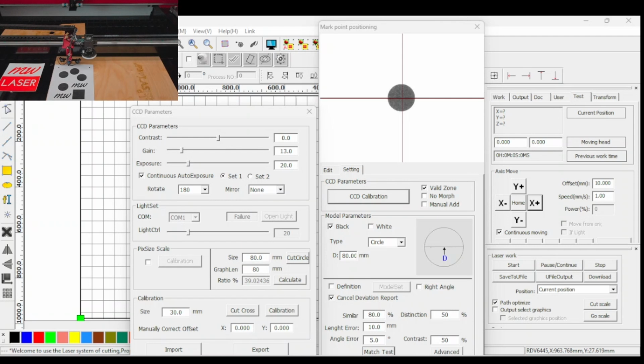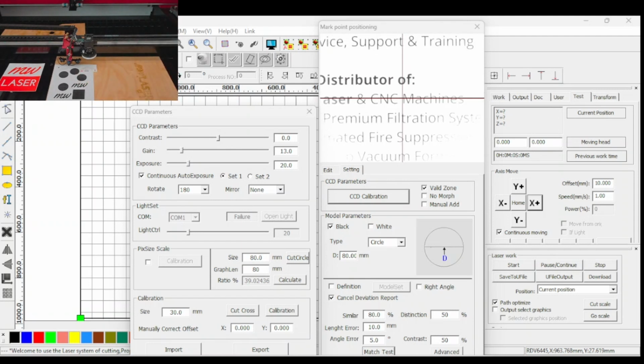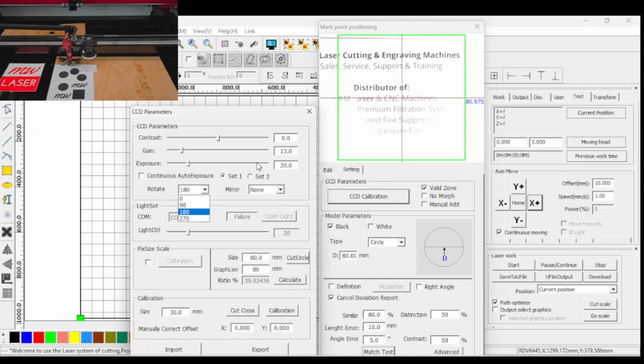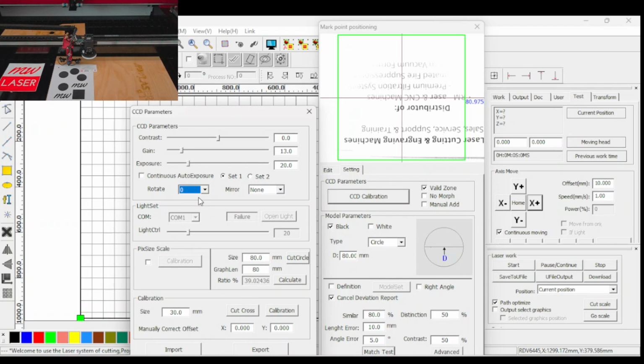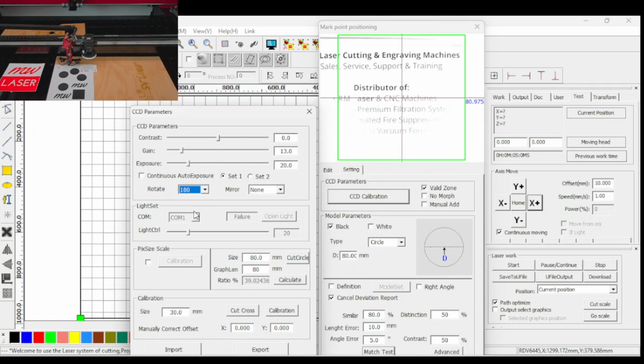All right, when you open up the CCD camera parameters, you can see the camera, you can adjust the contrast, the gain. You can also have continuous auto exposure. So this will adjust if the lighting in the area that you're working in adjusts. You can leave continuous on, but you can also adjust your exposure and things like that here. You can also rotate the image. So if what you're seeing was not clear or upside down, we could adjust it 180 degrees to make sure that the orientation is correct. So if it was set on 0, that's how it is in my machine, but I've adjusted it to 180 degrees. So again, we need to make sure that we have a clear image.